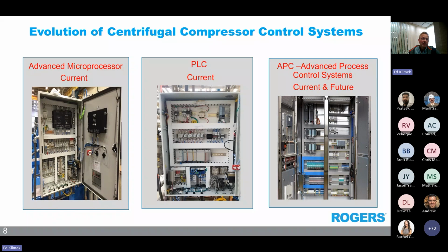And then you move into the advanced microprocessor, which is current today, which you see in a lot of centrifugal machines. You see a lot on recip and screw type compressors. That's more the transition to the digital PLC and DCS integration. They still exist today, and a good reason for that is proprietary control systems, more of what they call a black box control system.